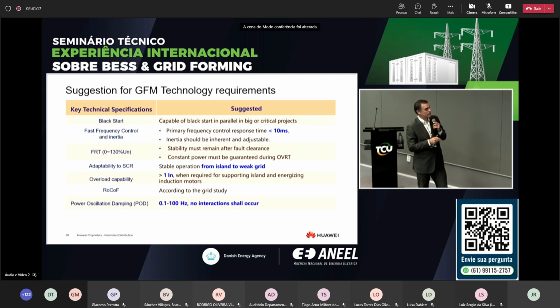This is mandatory to provide inertia, to be able to ride through faults, to work in very weak grid conditions, to provide overload capability for supporting islands or energizing induction motors, to help prevent rate of change of frequency, and power oscillation damping.